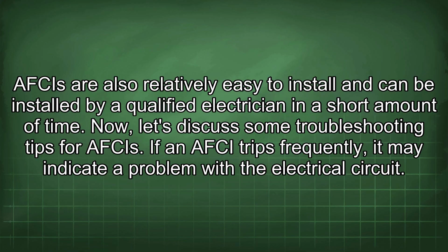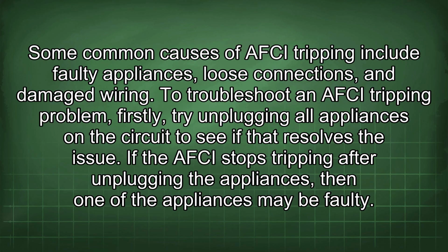If an AFCI trips frequently, it may indicate a problem with the electrical circuit. Some common causes of AFCI tripping include faulty appliances, loose connections, and damaged wiring. To troubleshoot an AFCI tripping problem, firstly, try unplugging all appliances on the circuit to see if that resolves the issue. If the AFCI stops tripping after unplugging the appliances, then one of the appliances may be faulty.